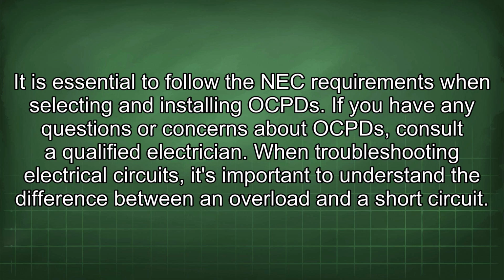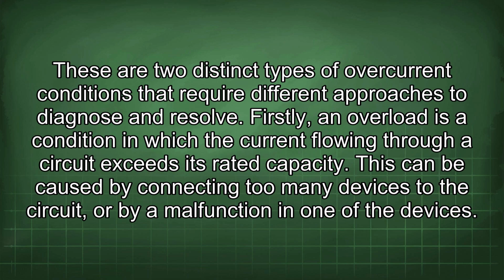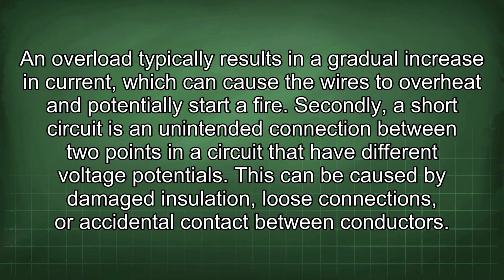When troubleshooting electrical circuits, it's important to understand the difference between an overload and a short circuit. These are two distinct types of overcurrent conditions that require different approaches to diagnose and resolve. Firstly, an overload is a condition in which the current flowing through a circuit exceeds its rated capacity. This can be caused by connecting too many devices to the circuit, or by a malfunction in one of the devices. An overload typically results in a gradual increase in current which can cause the wires to overheat and potentially start a fire.